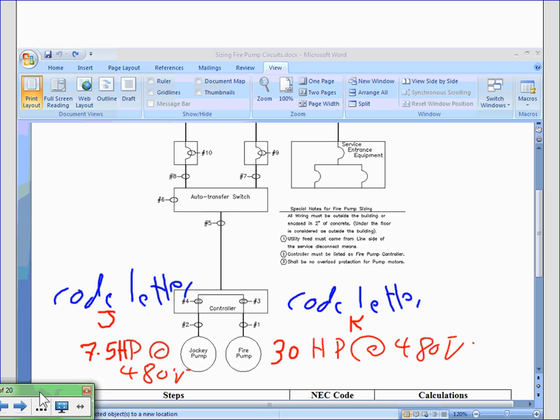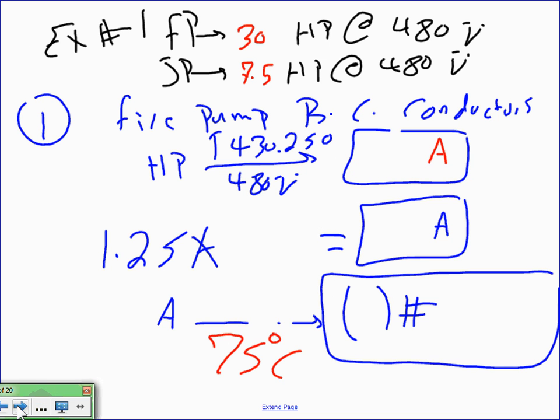Guys, our job as designers and engineers is to lay out the system. This is part of why they pay us, right? Everybody knows that. You're going to get from, be it, an auto transfer switch that picks the fire pump system or an auto transfer switch that picks the emergency system. I can't emphasize enough, we went through this example, the same calculation. All I did for the review, guys, is basically change the numbers.